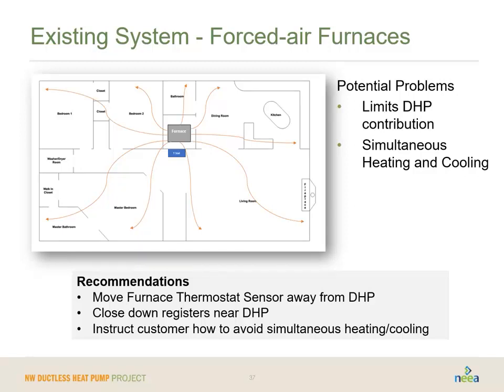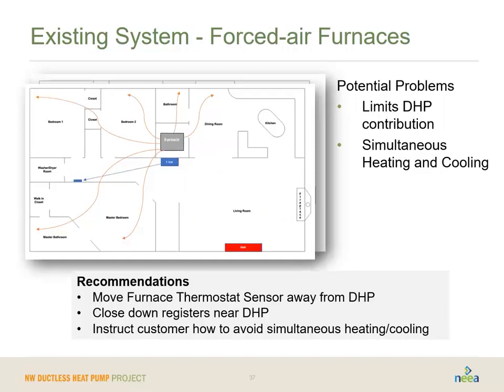You can also turn down the registers in the main body of the home a little bit. We don't typically do that for efficiency. We just do that so it's not competing with the heating and cooling that comes from the ductless heat pump. And then really instructing homeowners on how to work their system to maximize their benefit. So a future system may look a little bit like this. We've got the thermostat moved down the hallway. We've got the heating register shut off in the main body. We've got the ductless heat pump set up to do the lion's share of the work in the main part of the house.